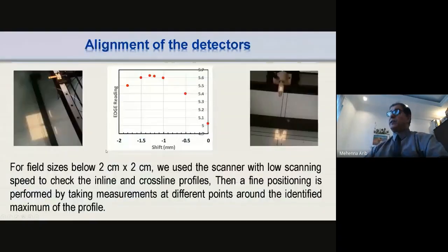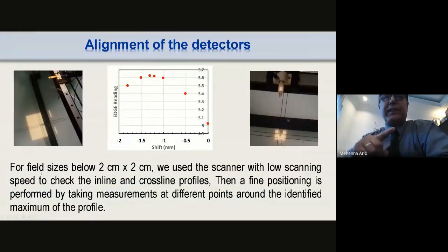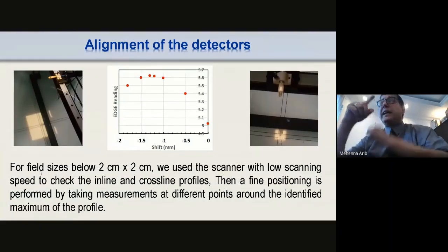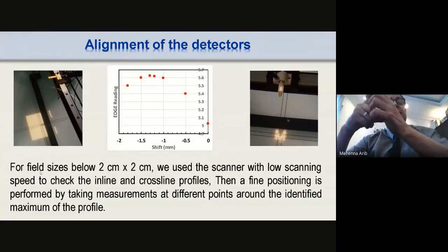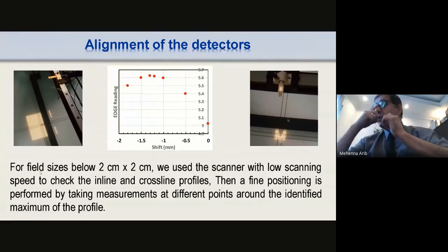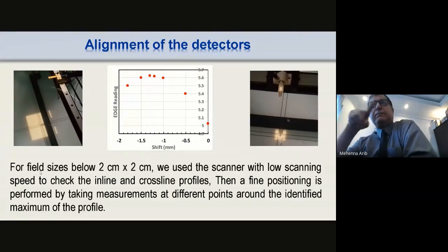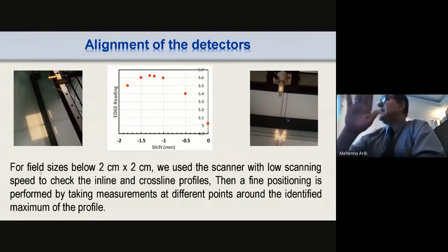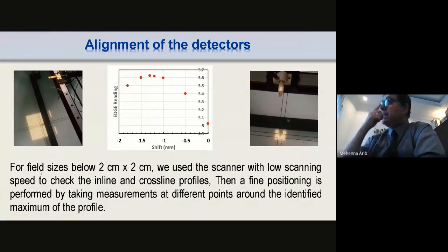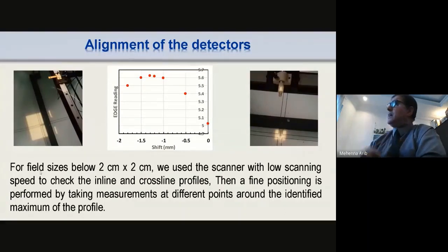So we were asked to investigate the behavior of these chambers for small fields and to check the validity of the correction factors. When it comes to measuring in small fields, you have to pay attention to the position of the chamber, especially for small fields down to 1 millimeter by 1 millimeter. If the chamber is shifted from the center of the field, then you may have very bad results. So what is the way that we did for the small fields? We start with the small fields. We just scan from the right to the left and position the chamber at the maximum position to be sure that you are in the center of your field.